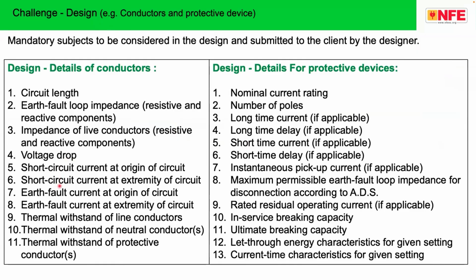Not only voltage drop, there are so many parameters to be considered while selecting the conductor. Circuit length, earth fault loop impedance, impedance of live conductors. Voltage drop is one of the parameters. Considering only voltage drop and selecting a conductor was the practice during the 1970s. Now we are in 2025. All these parameters for selecting the conductors are required. All these parameters for selecting the protective device are required.